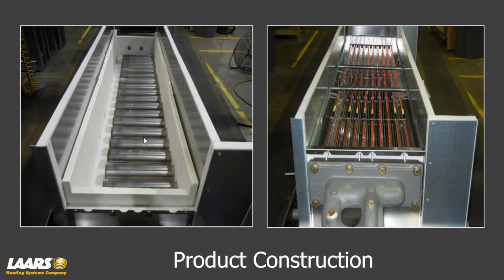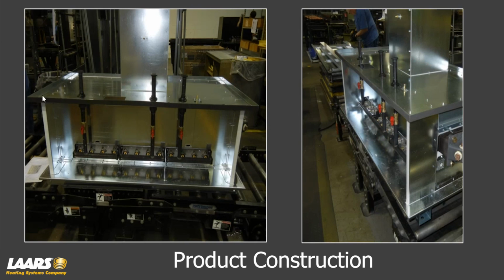So here's your image of your burners being suspended in position. Firing takes place in the chamber and then up through the heat exchanger. Next, they'll add the top plate. Now, I mentioned your gas train comes through the upper deck. There are rubber grommets on here. Why? Because this is a plenum. We're actually blowing air, so there's an opening right here.